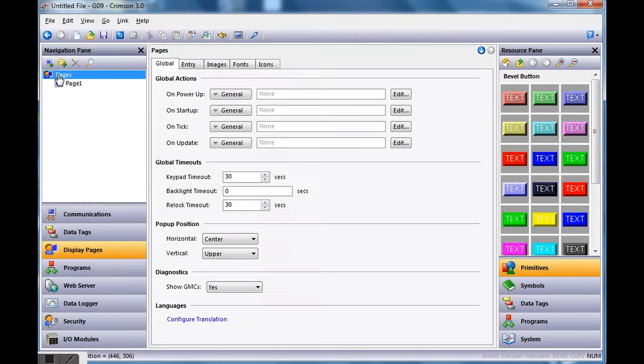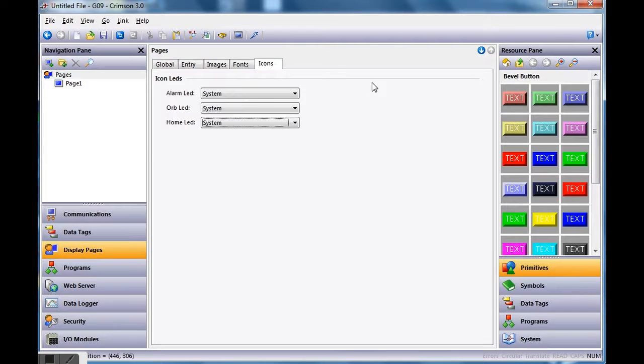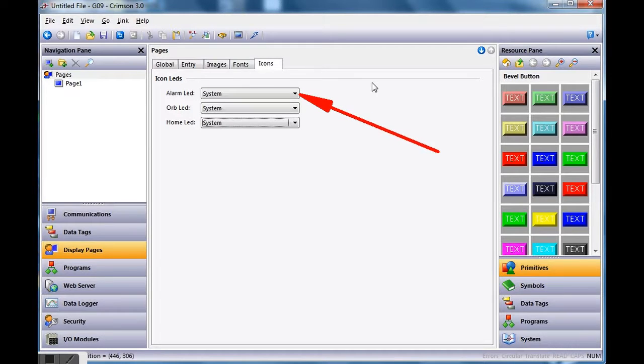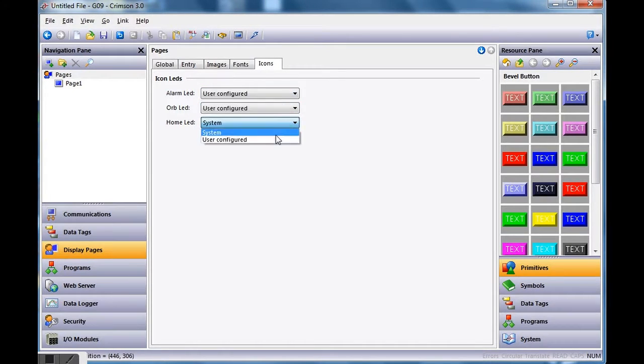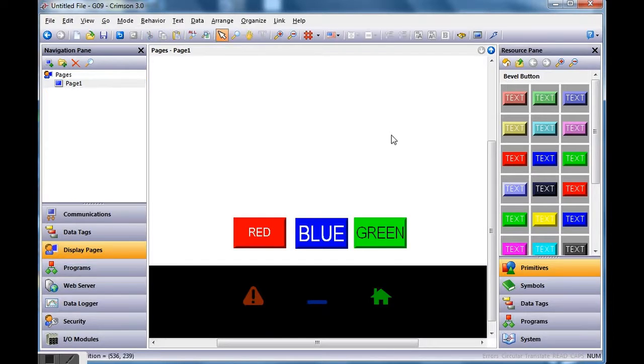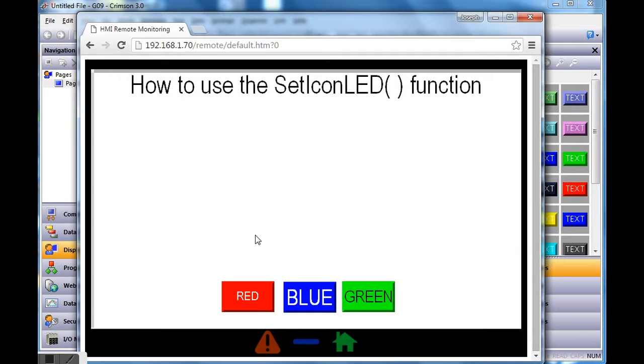To do that, click on the word Pages on the left-hand side, then go to the Icons tab — there's actually a tab called Icons. Currently they're set to System, which means if an alarm tag went high, the operating system would take over and blink that light automatically. Instead, I want to user-configure these, so I'll hit the pull-down and choose User Configure. That should allow me to use the SetIconLED function the way I want.